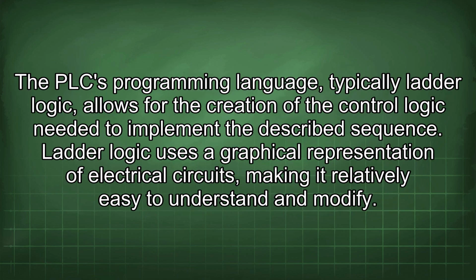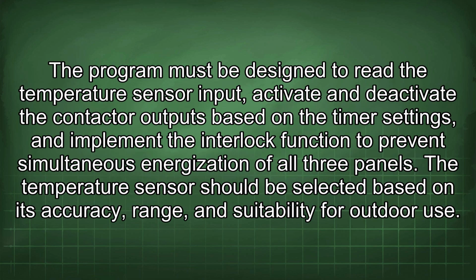The PLC programming language, typically ladder logic, allows for the creation of the control logic needed to implement the described sequence. Ladder logic uses a graphical representation of electrical circuits, making it relatively easy to understand and modify. The program must be designed to read the temperature sensor input, activate and deactivate the contactor outputs based on the timer settings, and implement the interlock function to prevent simultaneous energization of all 3 panels.